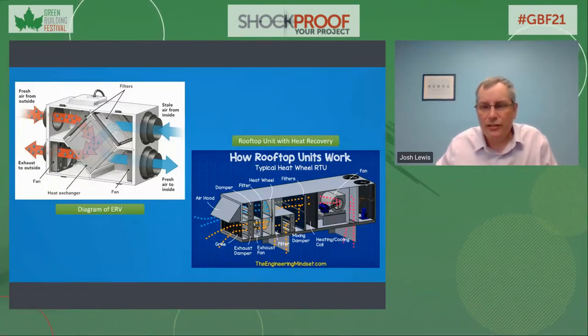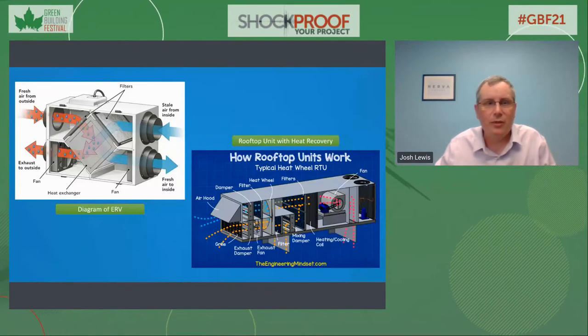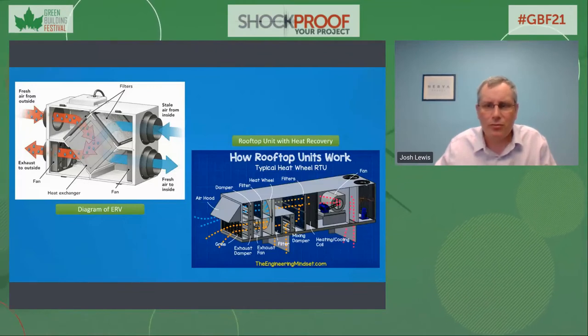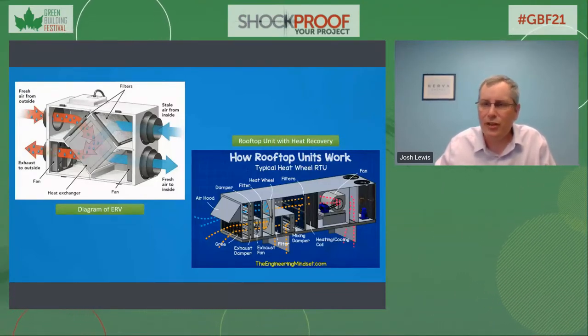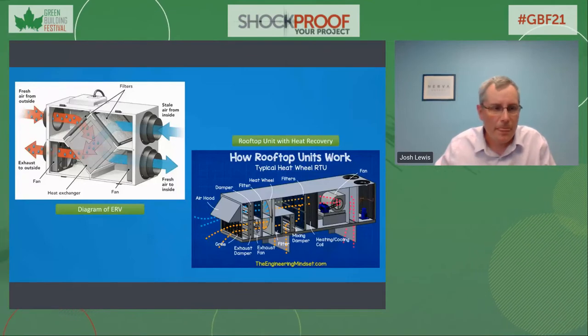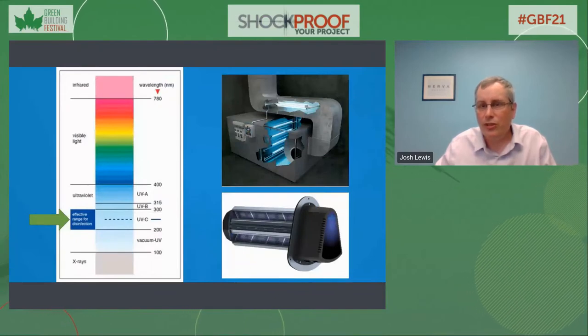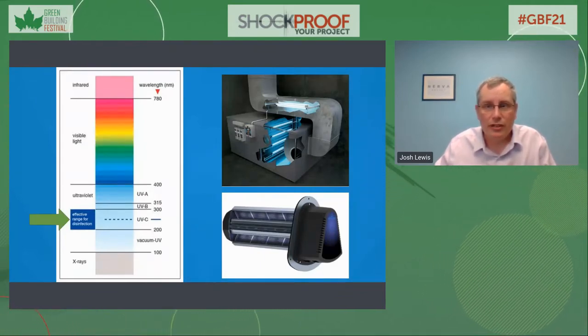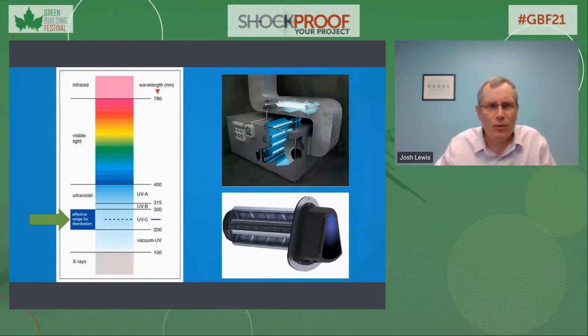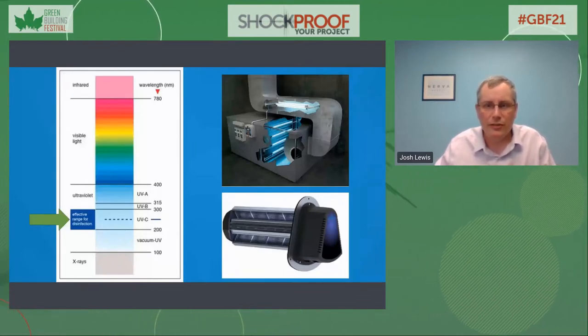While there are a lot of good practical actions to achieve a healthy environment contained within filtration and dilution, there are still two more key operational parameters, with the next one being purification. Purification in this case is defined as systems which clean the air of contaminants, excluding filters. So the most common type of air purification systems utilize ultraviolet light to kill biological contaminants in the air, including viruses and bacteria. Ultraviolet systems are not a new technology, but prior to the current pandemic, were mostly utilized in hospitals and food processing facilities.